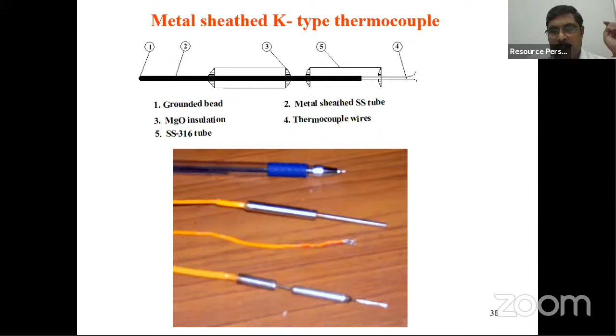One should know about the codes. These are the commonly available codes for representing the thermocouples. We follow the French code - from the fourth column you can see the K-type thermocouple is yellow, T-type thermocouple is blue, E-type is pink, and J-type is in ash color. Basically we follow the French designation.